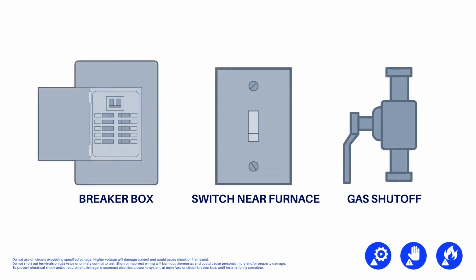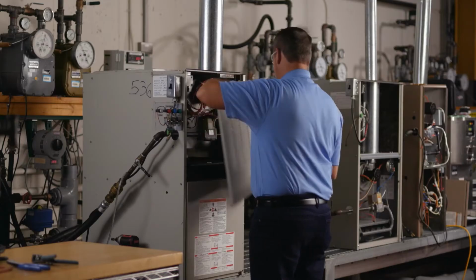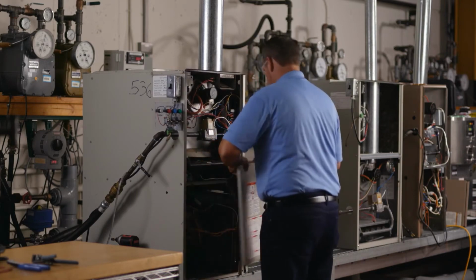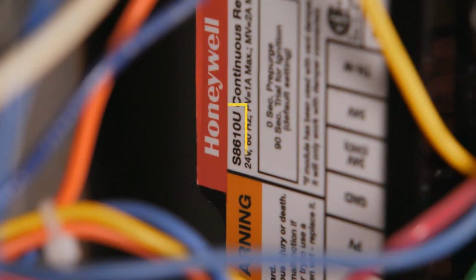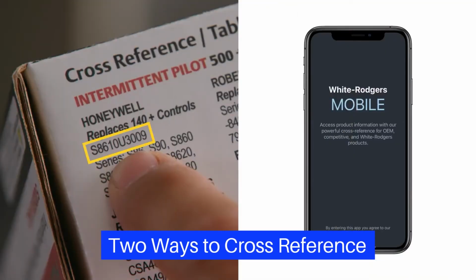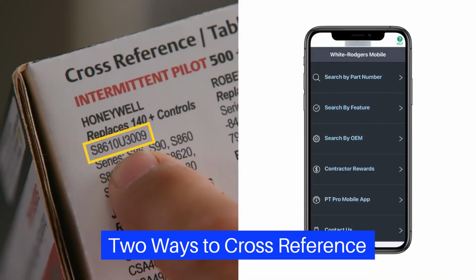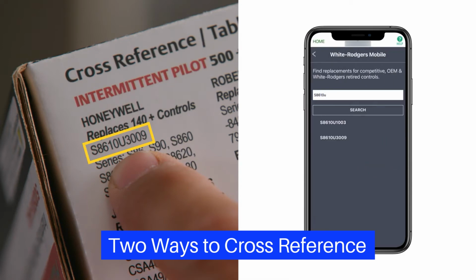First, ensure power and gas are disconnected prior to servicing the unit. Remove the access panel. Check the part number on the existing control and verify it as one of the 140-plus controls that can be replaced with the 50D50U-843. Use the cross-reference on the side of the carton or the White-Rodgers mobile app.